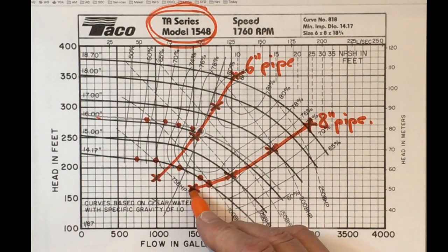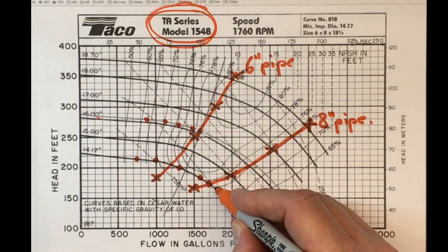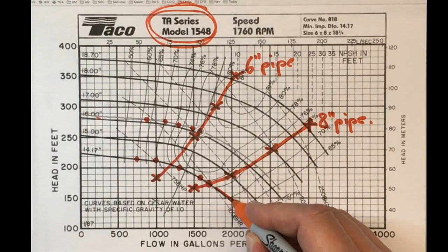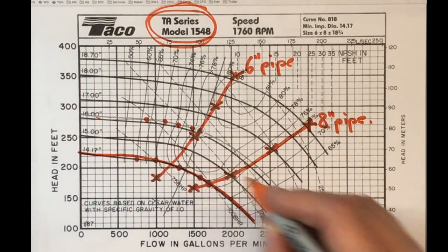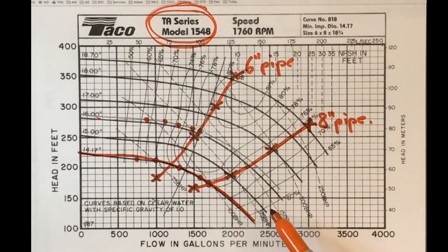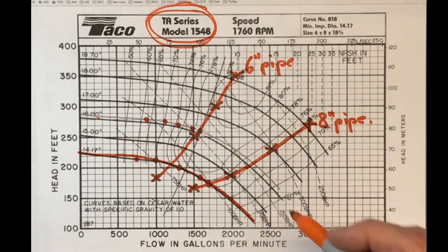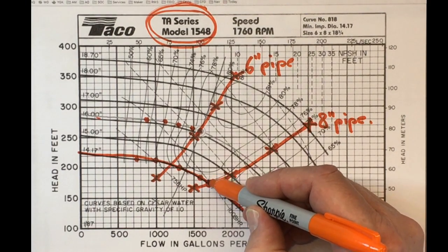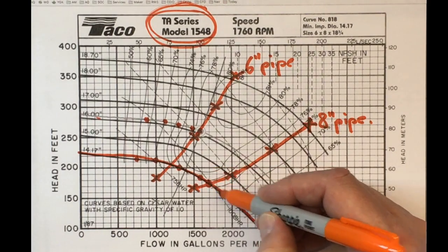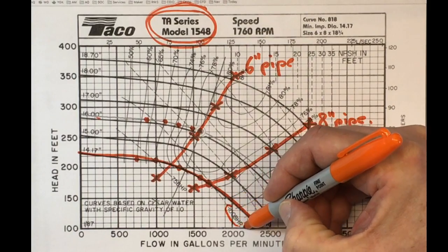And now that we've decided to go with the 8-inch pipe and the 14.17-inch impeller, we need to decide on what motor we're going to put on it. Now our expected operating point here has a motor horsepower requirement just a little bit under 100 horsepower.